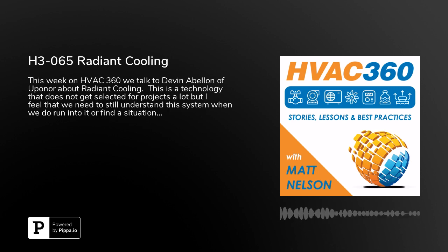Yeah, and you look at some of the studies that have been done, Lawrence Berkeley National Labs, the Pacific Northwest National Lab studies. When we talk about radiant cooling as a system, it's commonly coupled with dedicated outside air systems, because a radiant cooling system is only going to address sensible load. So you're always going to need a secondary system to provide code-required ventilation. This dedicated outside air system does a very nice job at decoupling the ventilation from the sensible load, and then it gives you that moisture control as well for the latent loads.